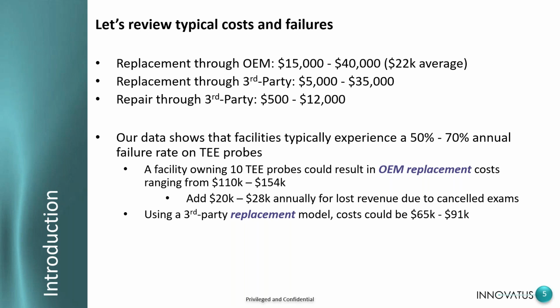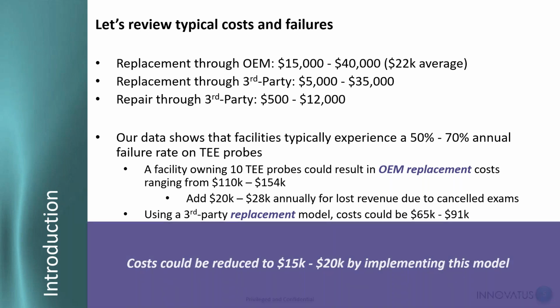And then we look at lost revenue. And beyond lost revenue, we also have to consider patient satisfaction. With a standard probe, if we're doing an abdominal exam or an obstetrical exam, it's not so mission critical usually. But with TEE probes, typically the patient's anesthetized. A lot of times we're in the operating room. And so if a probe goes down, we have patient satisfaction, we have physician satisfaction, you may have an anesthesiologist in the room, the patient may have to be rescheduled. So there's a cascading effect, negative effects from a TEE probe going down. And using a third-party replacement model, the cost could be anywhere between $65,000 and $91,000. And again, you recover all those patient satisfaction factors, such as patient care and throughput and revenue for the department.